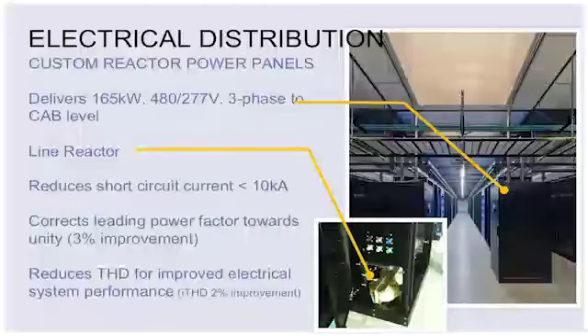We have installed reactor power panels, or RPPs. At 480 volt 277, we needed something to contend with the leading power factor, and also allows us to control some of the harmonic dissonance. This is also the location where we are able to backfeed anything that might require service. We have cam lock connections on these RPPs so we're able to backfeed and service the equipment. We do all our distribution with overhead bus duct and busway, with power panel plug-in tap boxes that allow us to adjust per the server requirements.